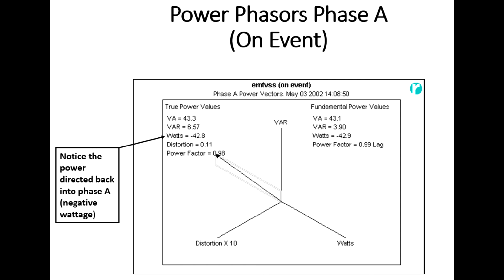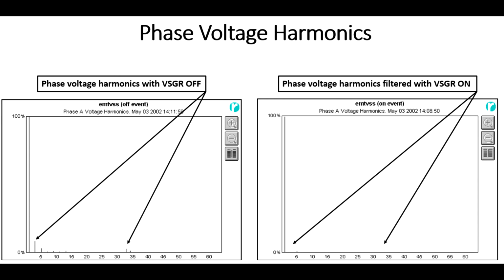equalize the phase voltages. We started out talking about power quality having to do with harmonics. These are the harmonics of those events. We'll see on the left graphic a relatively high amount of third, a little bit of fifth, a little bit of 11th or 13th rather, 33rd harmonic, and this was the electrical noise in that power system. When the voltage correction was engaged, all of them were below 1%.